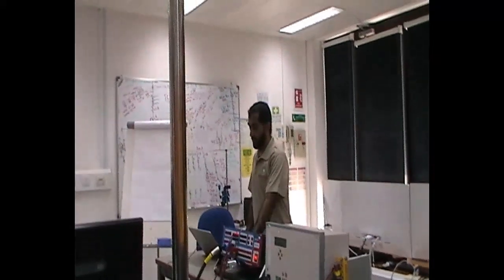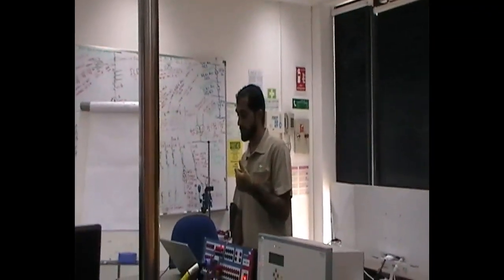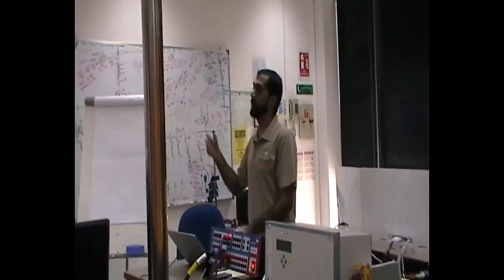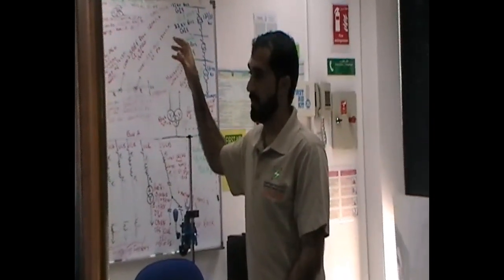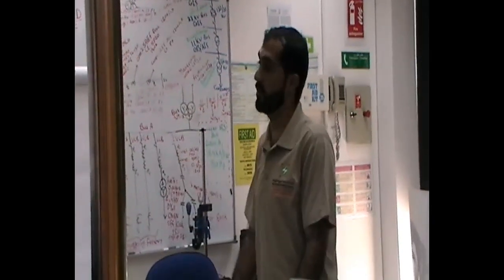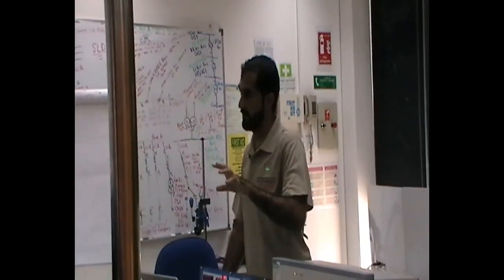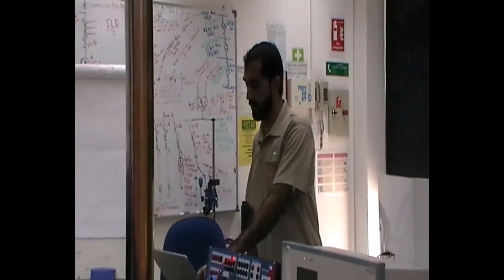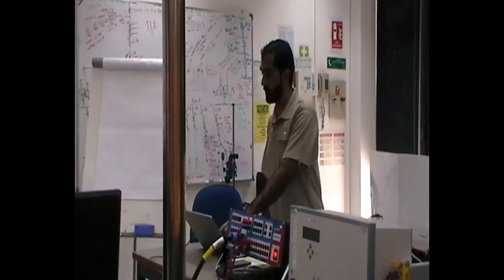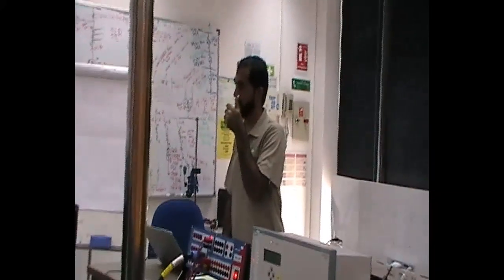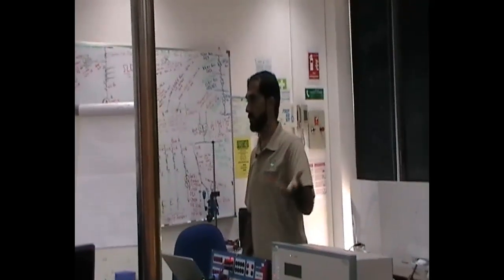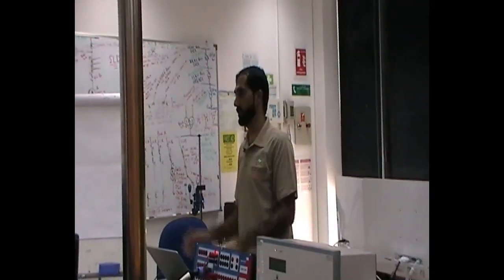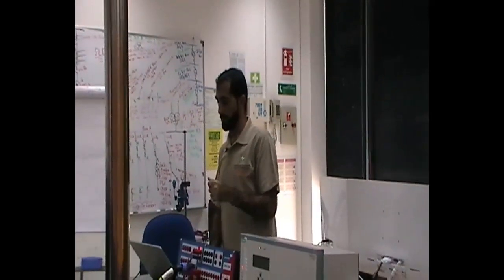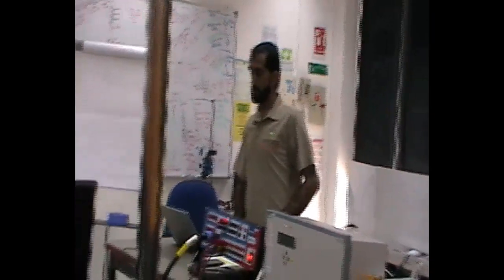What about the timing, will it be considered for zone 1 or for the backup? Basically, in this case, 400 milliseconds is given so that it gives time to the particular relay in that line. That's why I've given 400 milliseconds. Otherwise, I could put it at 0 if I'm sure the fault is in the line. When I am sure that the fault is in the line, I put the time for zone 1 as 0 milliseconds. The same goes if there is differential, which is unit protection. The timing is always 0, because I'm sure it's in the particular unit. So this one is backup for the differential. Zone 1 is backup for the differential.